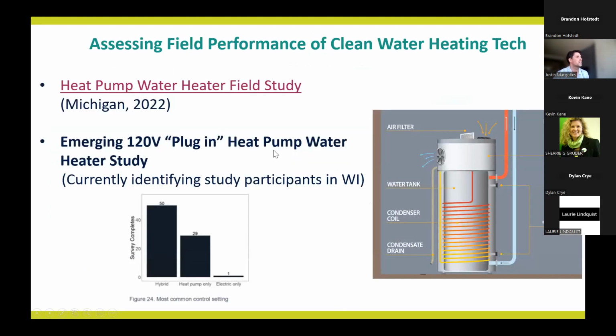Just a couple last points on clean water heating tech. Slipstream did a field study on heat pump water heaters as well. The main point is they're performing pretty well up to their rating. On the image at the bottom, there are three modes on those traditional heat pump water heaters: hybrid mode, heat pump only mode, and electric only mode. Heat pump only mode is ideal and most efficient, but some homes with a lot of hot water demand or more people in the house may want to use hybrid mode, which relies on some backup electric resistance, shown in the picture on the right as those coils.